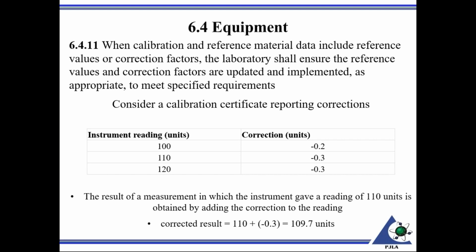Often you should see the data there, where we have some examples at the bottom. Perhaps that's a temperature standard. You have a certain tolerance that you base the pass-fail on. However, very seldom are you going to see that equipment being directly on nominal. There's normally a deviation from nominal that's specified within the calibration report. So the correction factor is when you apply that deviation.